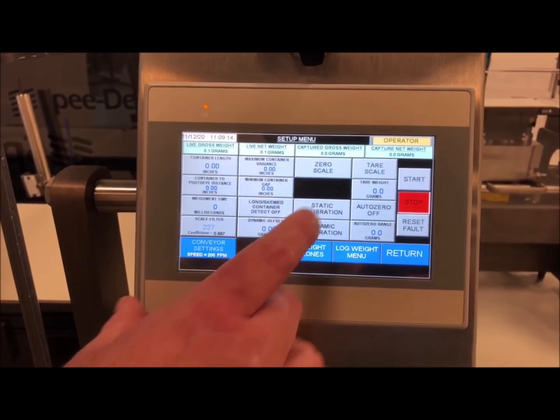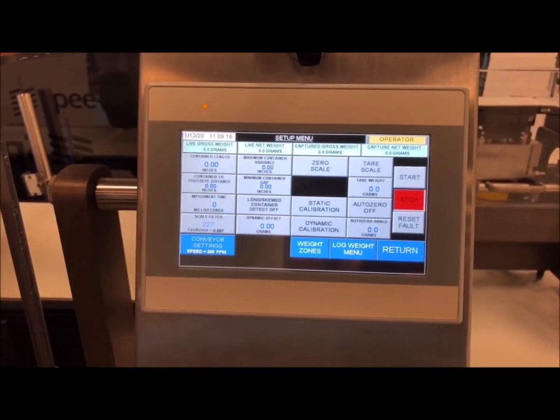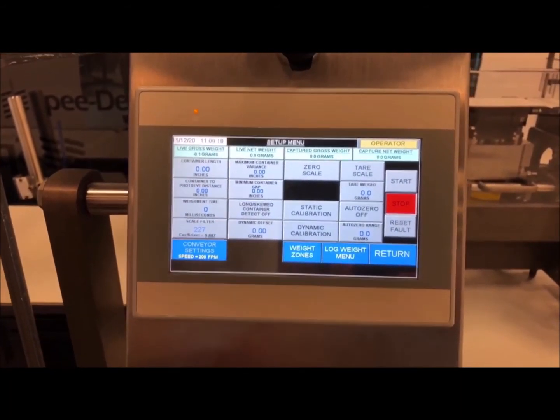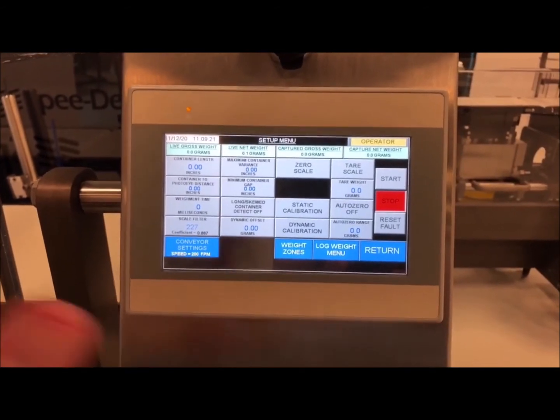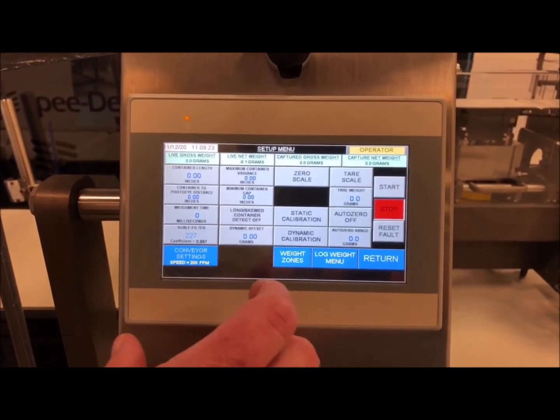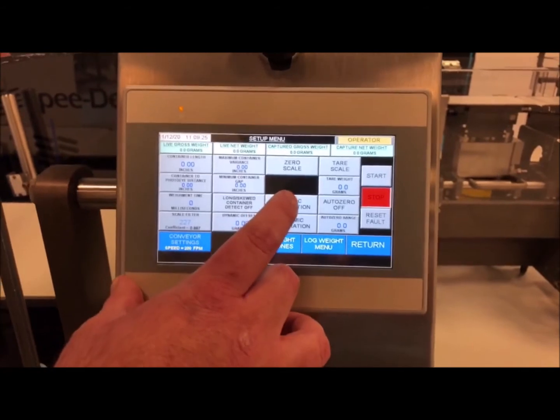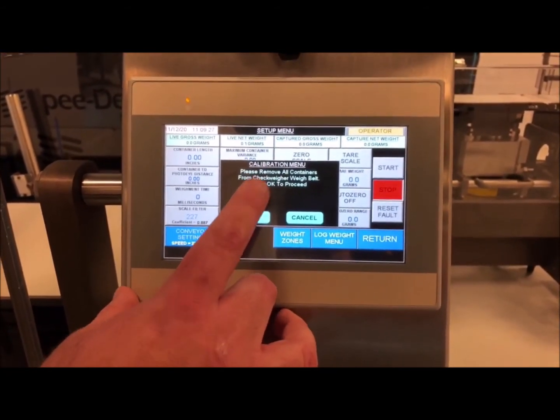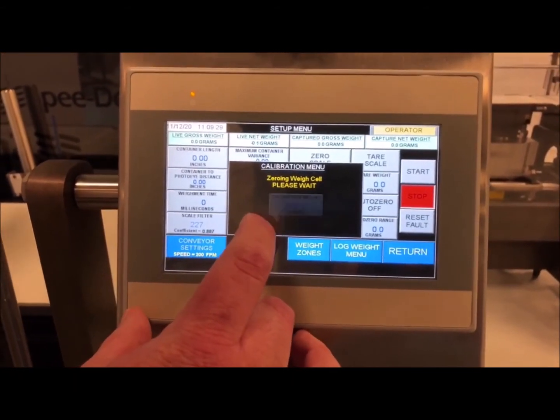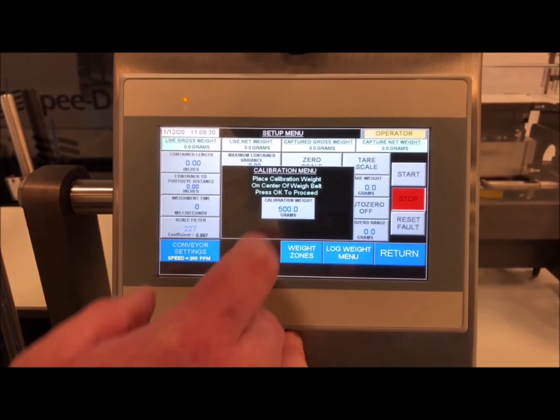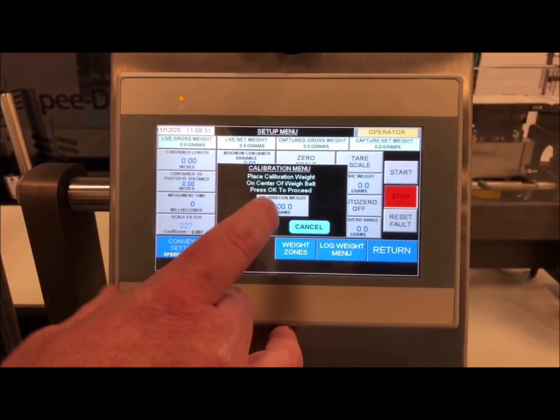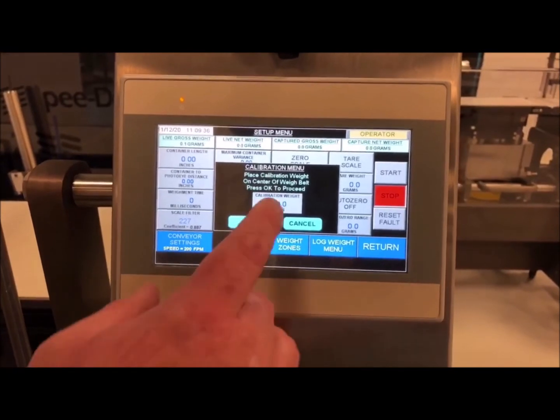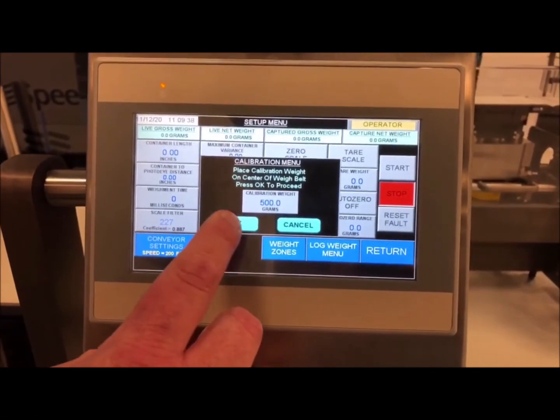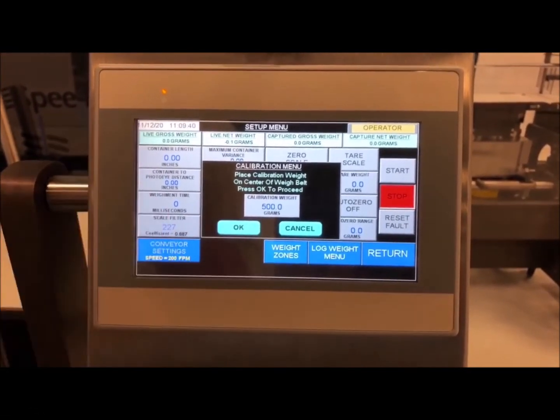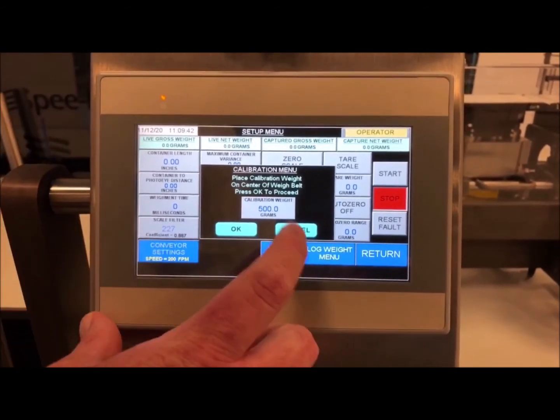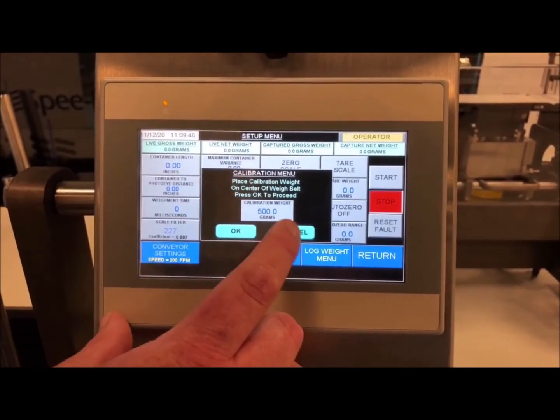With static calibration, you use a certified calibration weight, such as a 500-gram calibration weight you can pick up on Amazon for about $20 to $30. You go into static calibration, press OK, and it zeroes out the scale. You double check that the weight input matches your calibration weight, set that right on the load cell, and press OK, and it calibrates to verify the load cell is reading the correct weight.